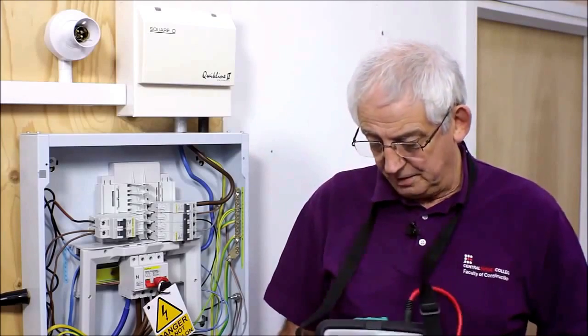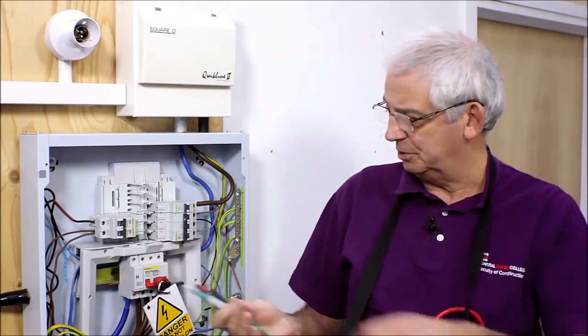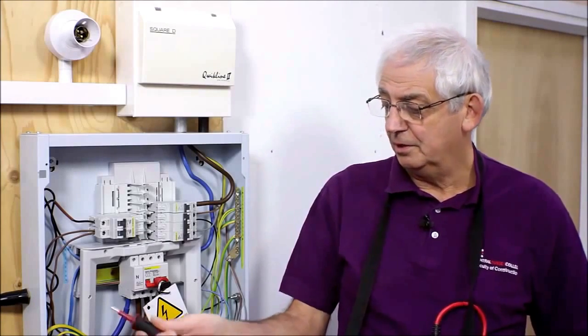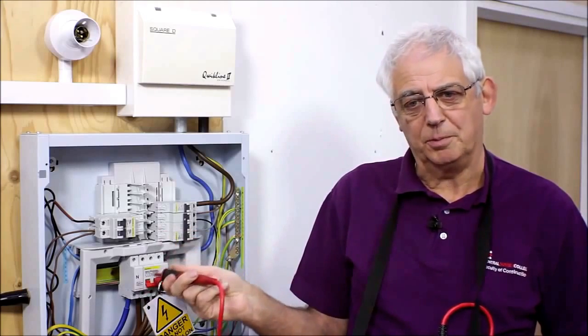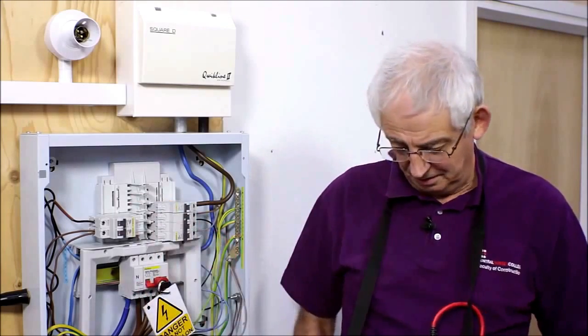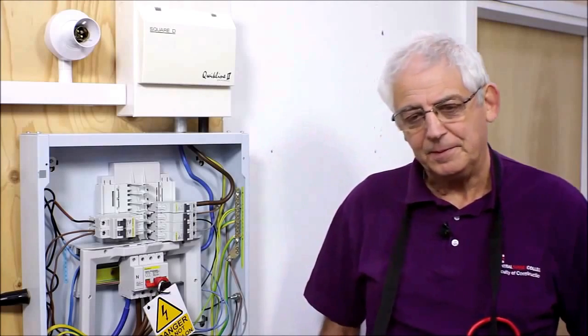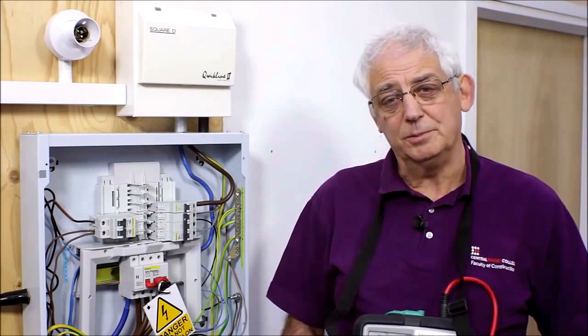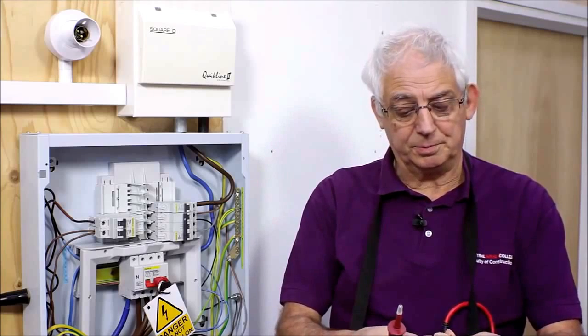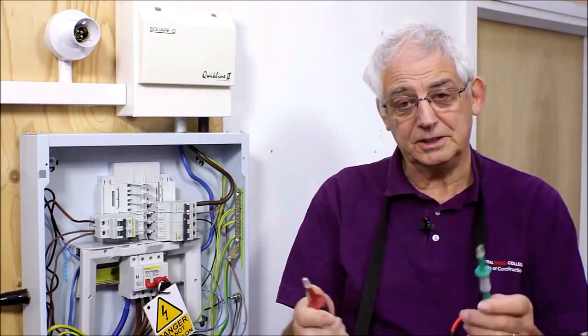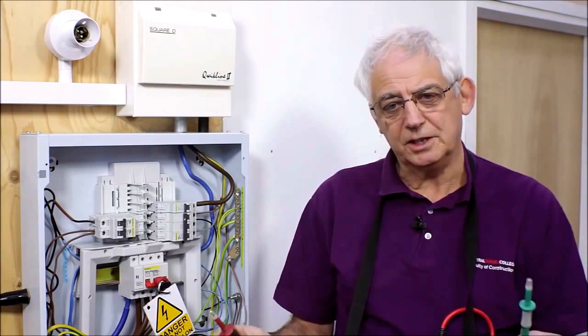If you're not careful, it can be very difficult trying to hold probes on and push the button at the same time. I've got a special probe here which has got a button on the end of it which allows me to operate the device from the probe, which is obviously a good idea, makes life a lot easier. One of the first things I need to do when I'm carrying out an insulation resistance test is to make sure, of course, the probes are in good condition, the ends of the probes are protected to comply with GS38, because this is really a 500 volt test. GS38 applies to any equipment over 50 volts.